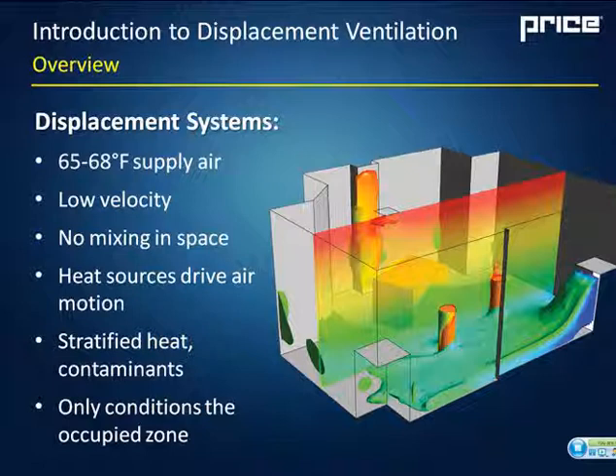And along the floor or right at the exit of the diffuser, it's around 65 to 68 degrees. So there's significant stratification or temperature gradient across the room. Now what that does is traps all the heat at the ceiling, and it also traps contaminants there. And because we're not using high velocity diffusers in the ceiling, we're not mixing all those contaminants and all of that heat back down. So it's not only more efficient in terms of indoor air quality, it's more efficient in terms of cooling.